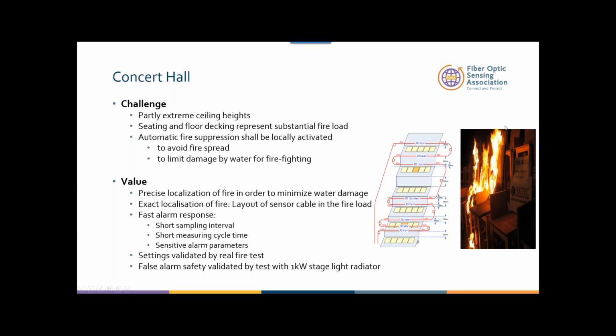To take it to the next level is similar to the Eisenhower tunnel. We call this performance-based. Why is it called performance-based? At the end of the day, there is a lot of regulation, but if you're not sure the regulation is meeting what you have to do, you go back and you do a trial and do a test before setting your alarm. Here's an example in the picture on the right. They tested an area, they tested a seat, to detect what the temperature level is and what the rate of rise can be at that location. And then you can say, we move forward with the project, and they installed it everywhere. And the ability to set this alarm based on the performance test done prior to the installation is quite important.